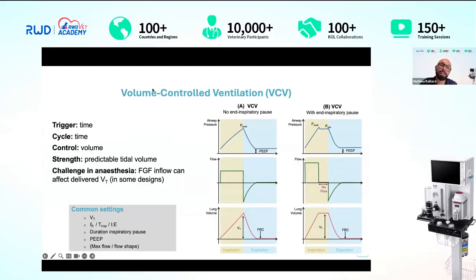In volume control ventilation, my trigger is the time and my cycle is the time. So I decide the duration of inspiration. I decide when it starts, when it stops. And in volume control ventilation, what I decide is essentially my tidal volume. I decide a tidal volume, but the ventilator understands a flow over time. So once the tidal volume is decided and the duration of the inspiration is decided, the ventilator will convert that into a regular square wave of a flow throughout the duration of the inspiration.